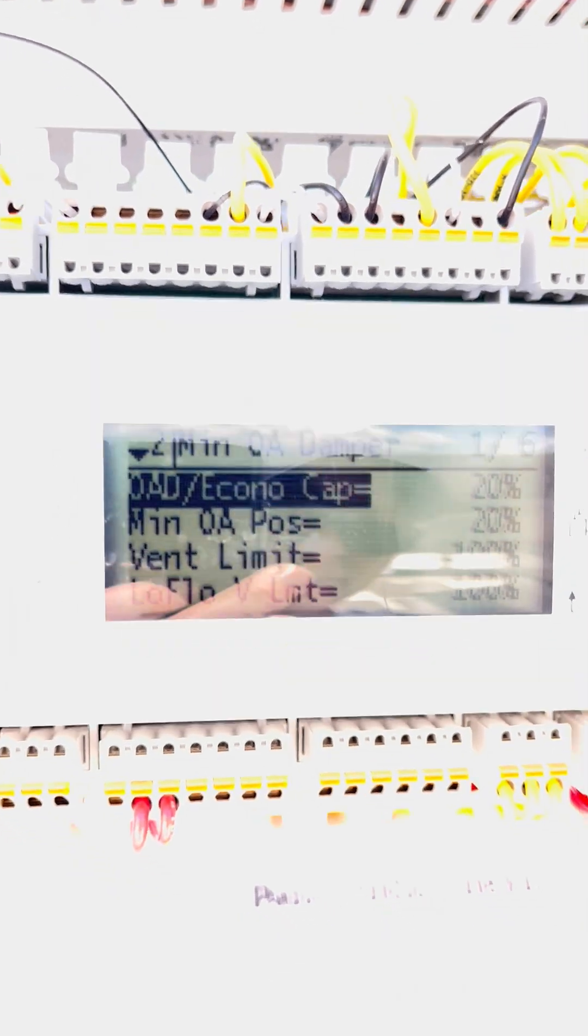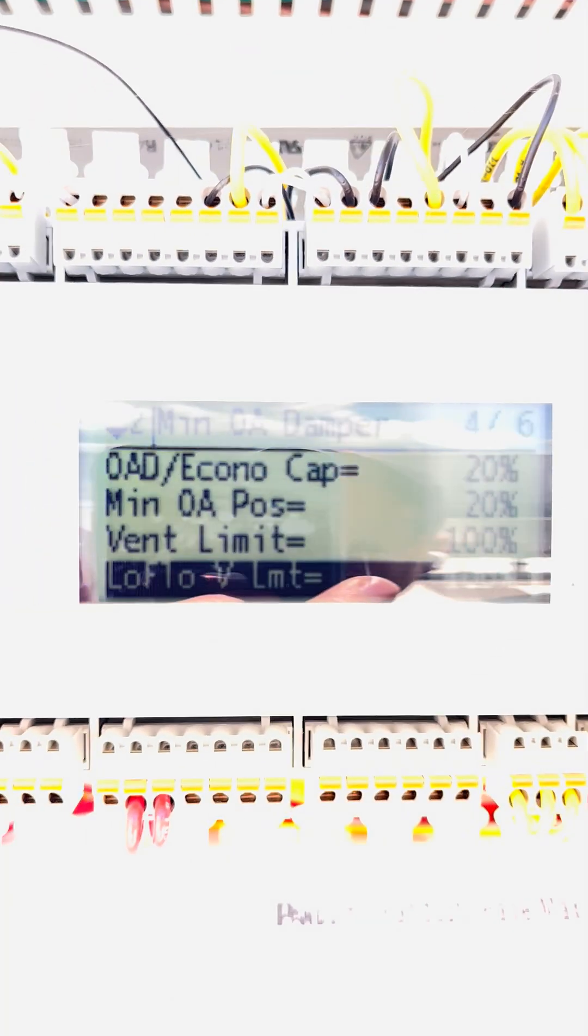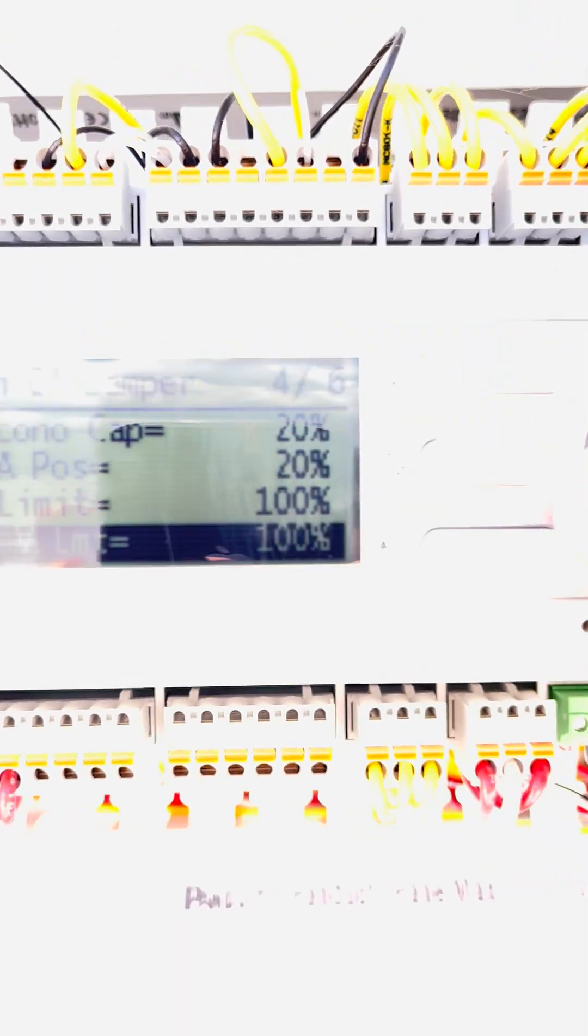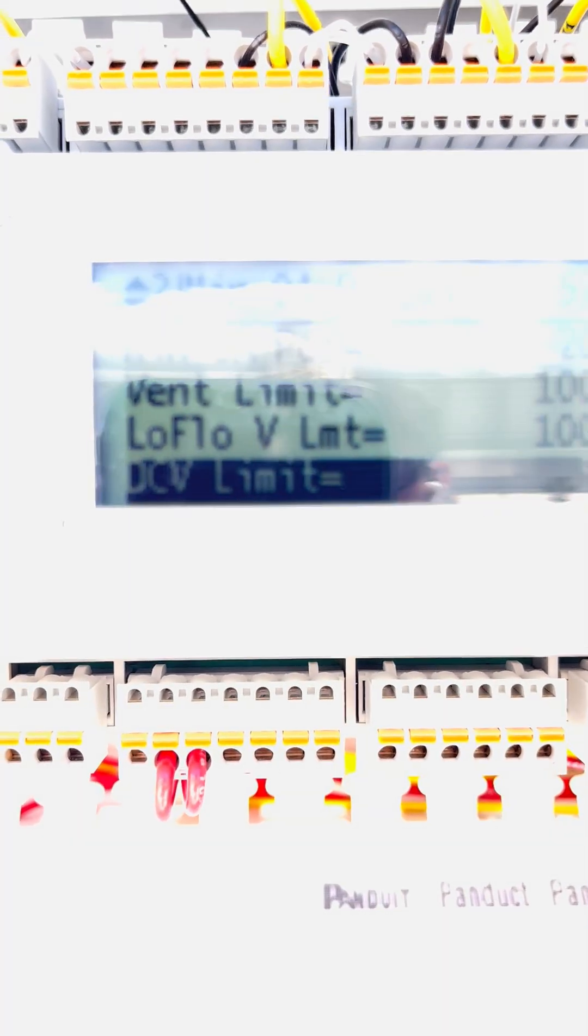Now, if I go down, we want to make sure that we set Vent Limit to 100%. We want to make sure we set low flow V limit also to 100%. And then the last one, which is your DCV limit, we want to set that to 5%.